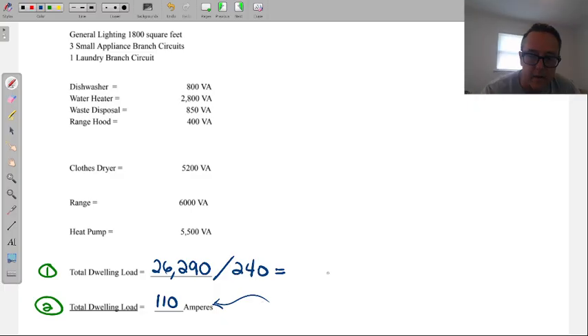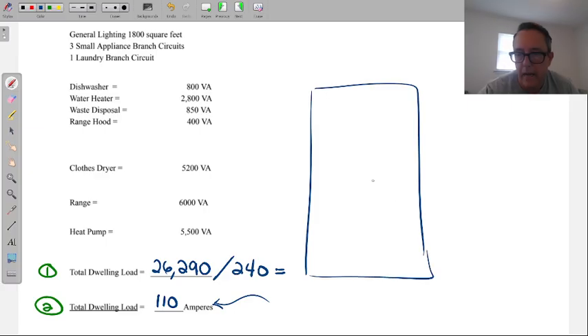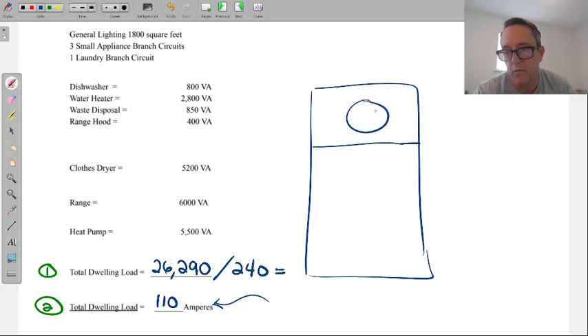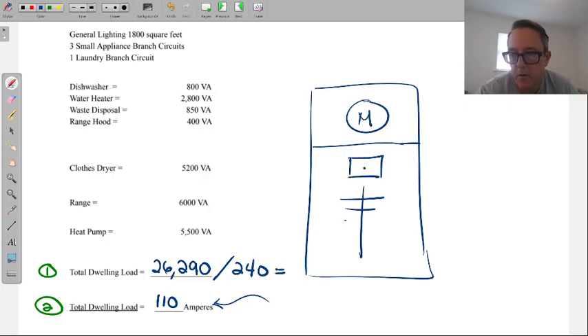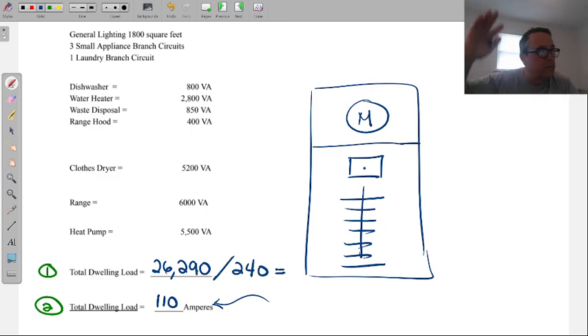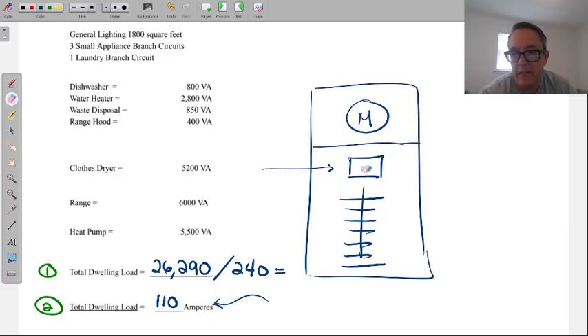The second reality is it's very hard to find a 110 main breaker system, especially if you're buying the combo panels that every electrical company uses for dwelling units these days — they come with the meter setup, the main breaker, and all your little breakers below, in whatever spaces you need. But if you go to Home Depot, Lowe's, or supply houses, it's very hard to find one at 110. The most likely size you'll find is 125, so we're probably already going to the next size breaker in real situations.